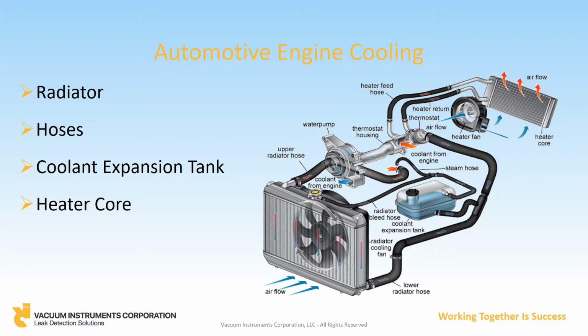Rubber hoses and the plastic expansion tanks are usually tested from a few cc per minute up to 50 cc per minute, primarily using air leak testing methods or perhaps handheld tracer gas sniffing. Finally, heater cores typically have a leak rate specification of 0.5 to 1 SCCM and are tested with either a hard vacuum or accumulation system, depending upon the required production rate.